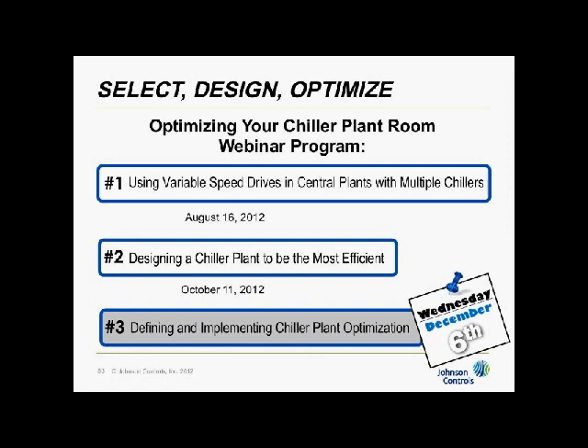What is the best cooling tower delta temperature which should be obtained according to your experience? I assume you're talking about the range across the tower? I wouldn't say there's necessarily that so much as you may be really talking more about the approach. What is the best approach? If I start with a 78-degree wet bulb and I have an 85-degree condenser water, that's a 7-degree approach. What's the best approach?